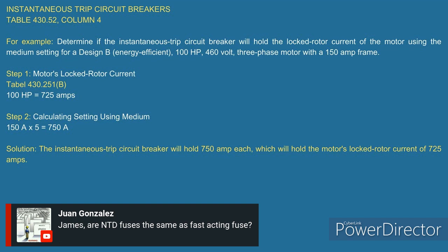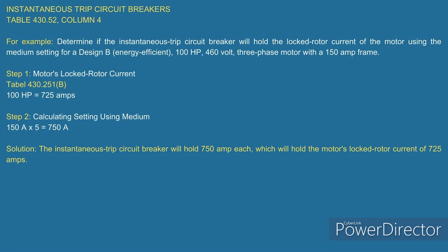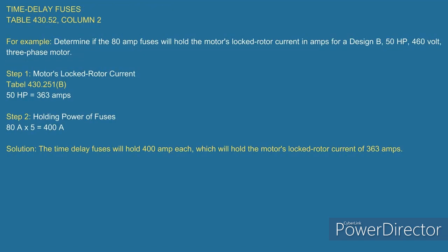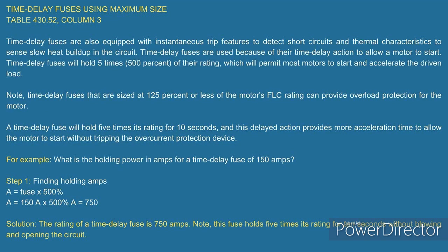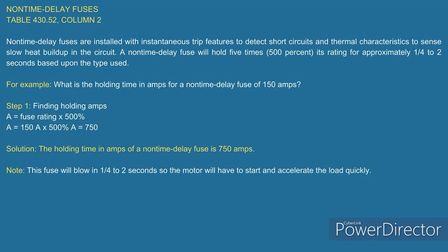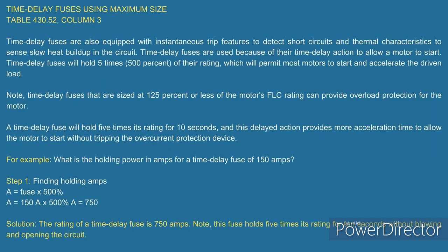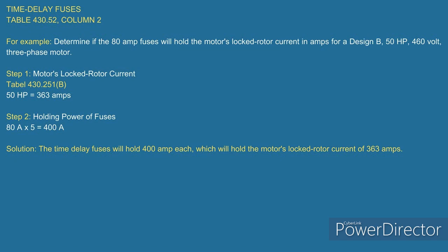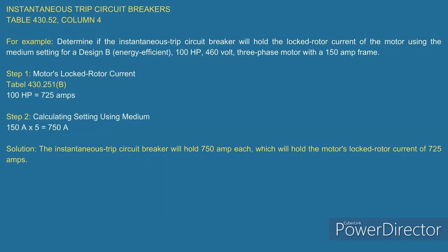Looks like Juan is lighting you up. Is a non-time delay fuse the same as a fast acting fuse? Well, that depends, because it depends which type of non-time delay fuse you're putting in. If you look back here, one of the things we tell you right off the bat is its rating is for approximately what, a quarter to 2 seconds. So if it's operating at a quarter second, yeah, that's a fast acting fuse. Same with different types of overcurrent protection devices, could be a circuit breaker or something like that. It depends on what type of fuse you buy, but yeah, that could be a fast acting fuse.